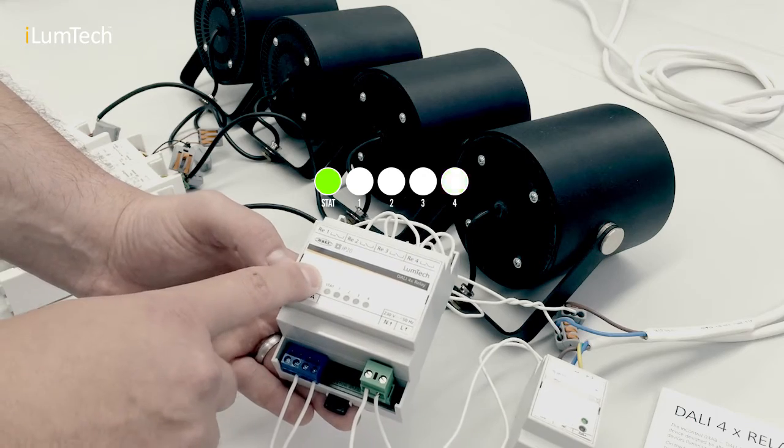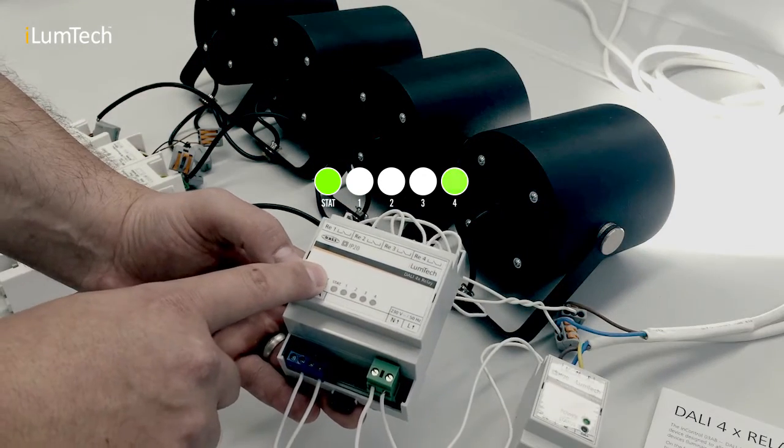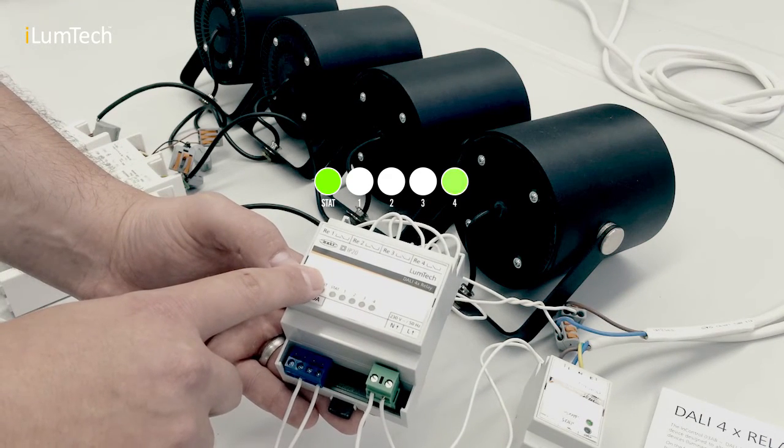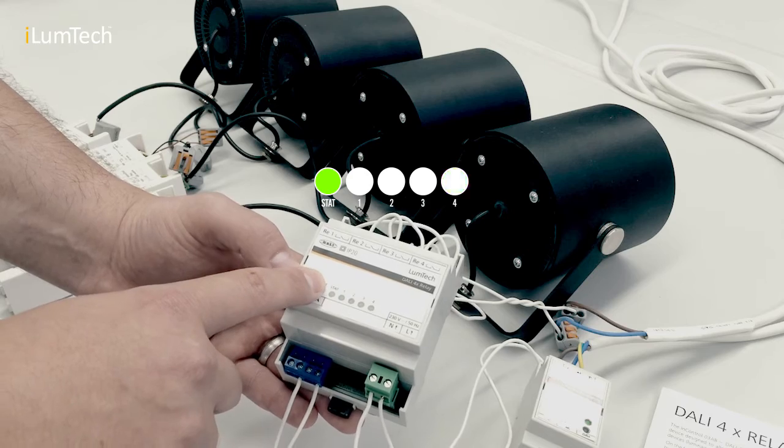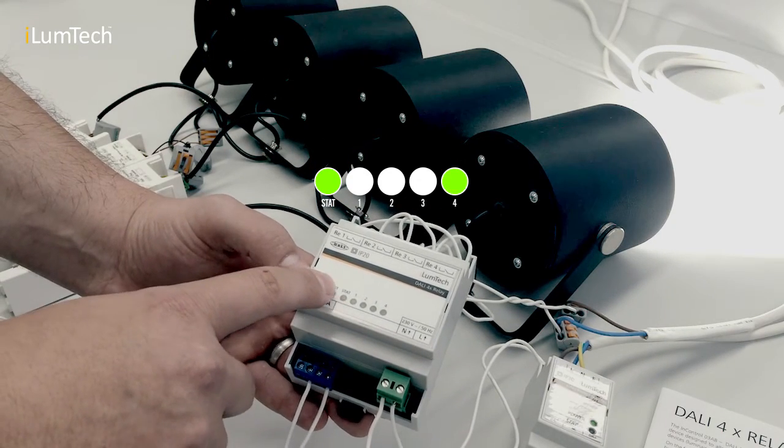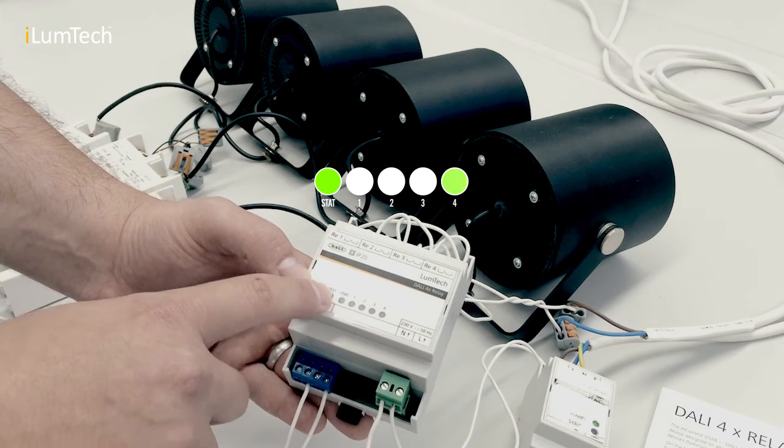Pressing and holding the push button for the selected relay contact changes its state. The current state of the selected relay contact is indicated by different ways of flashing. When the contact is closed, the LED indicator flashes with a predominantly ON state, while an open contact is represented by the LED indicator flashing with a predominantly OFF state.